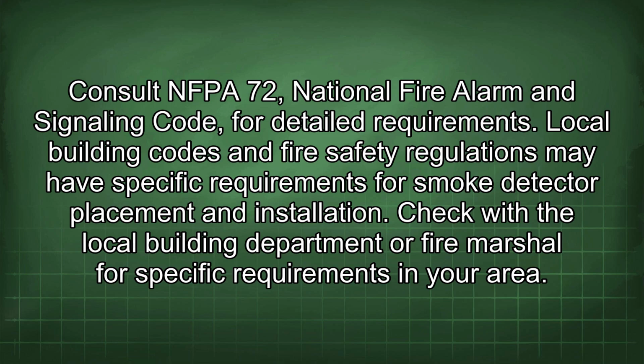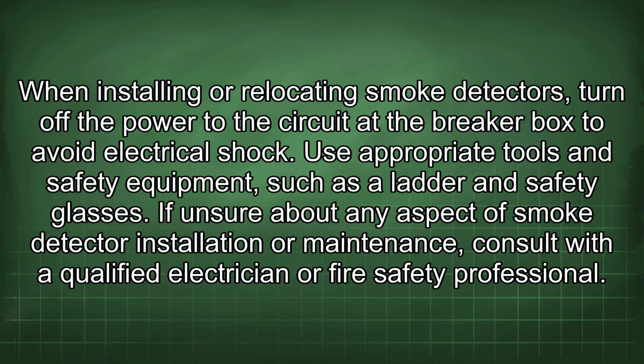Local building codes and fire safety regulations may have specific requirements for smoke detector placement and installation. Check with the local building department or fire marshal for specific requirements in your area. When installing or relocating smoke detectors, turn off the power to the circuit at the breaker box to avoid electrical shock. Use appropriate tools and safety equipment, such as a ladder and safety glasses. If unsure about any aspect of smoke detector installation or maintenance, consult with a qualified electrician or fire safety professional.